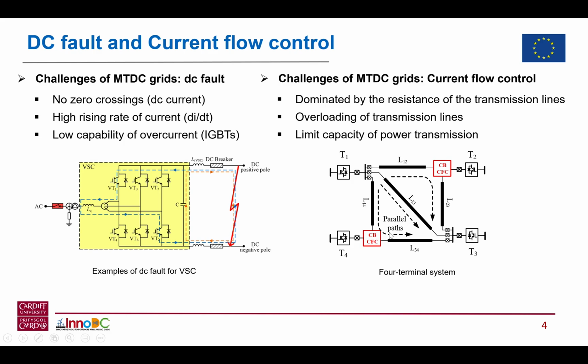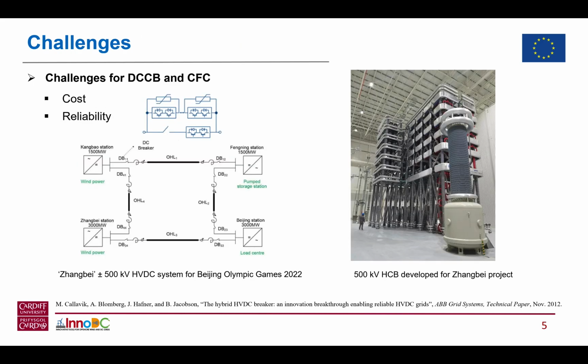In order to address such challenges, DC breakers and CFC controllers have been proposed and widely discussed. But among all the available schemes, there is still a problem in that the DC circuit breakers and the CFC controllers consume a lot of IGBTs, which increases the system-level cost. There is an example on the right in the figure, which is only one hybrid circuit breaker, built for the Zhangbei project. The DC breaker is quite a large device. It consists of a lot of IGBTs. So the cost and the reliability are still challenging for building such a big device.